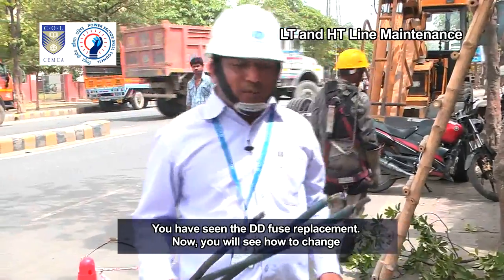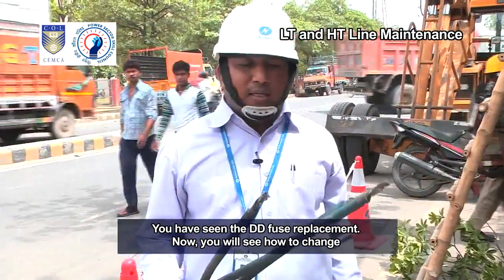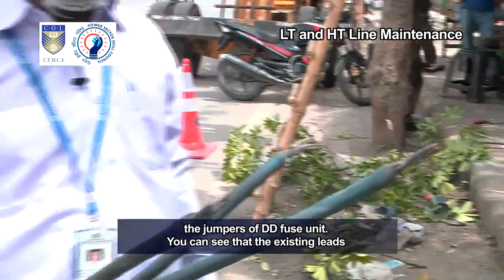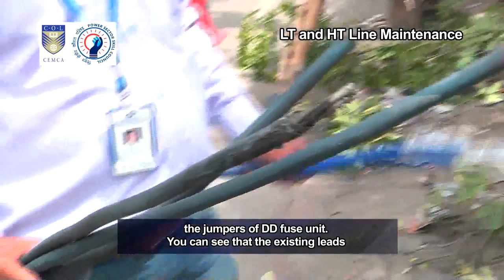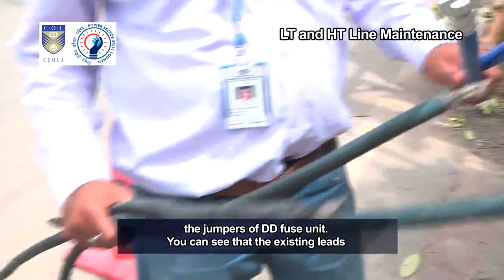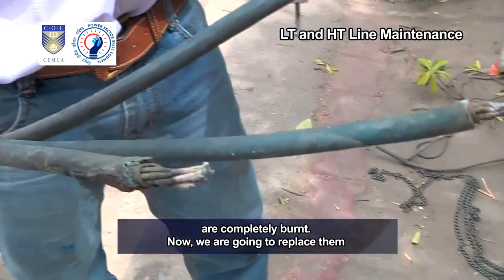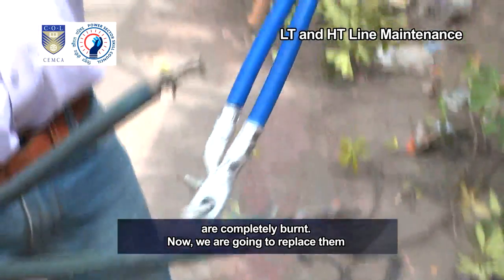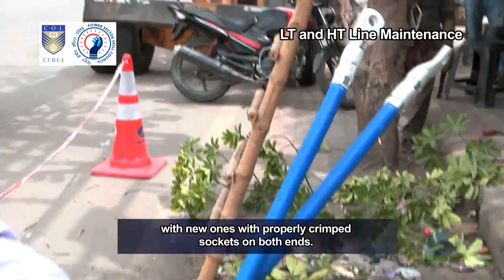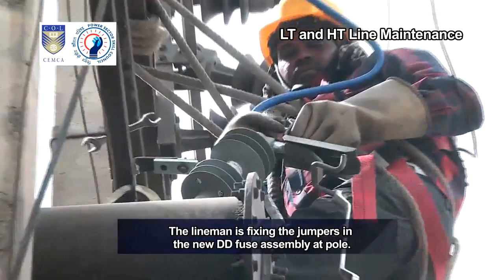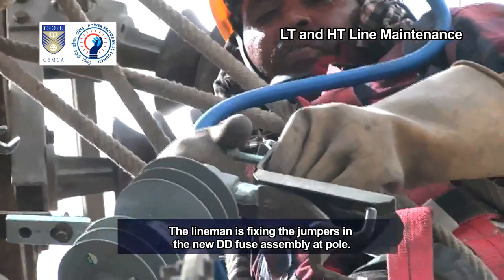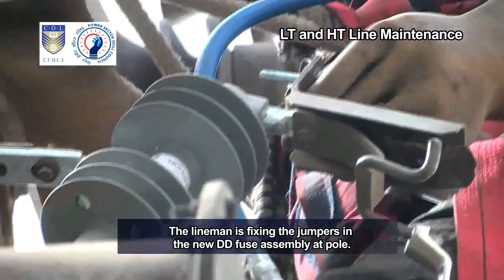You have seen the DD fuse replacement. Now, you will see how to change the jumpers of DD fuse unit. You can see that the existing leads are completely burnt. Now, we are going to replace them with new ones with properly crimped sockets on both ends. The lineman is fixing the jumpers in the new DD fuse assembly at pole.